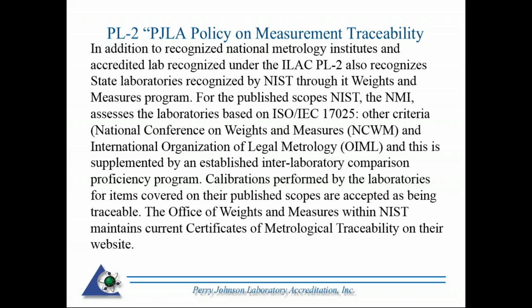They have been assessed by NIST Office of Weights and Measures. Their standard, their document, which is NIST Handbook 143, correlates to 17025. So we do state that. The state lab system was originally started for commercial weights and measures, buying and selling over scales, gas pumps, those sorts of things. It still is very integral in commercial, but they've also been deemed regional NIST labs, particularly in the area of mass. So states were started with mass, length, and volume standards donated by NIST.